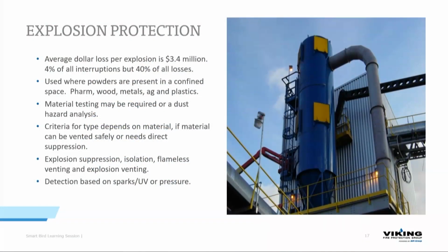So if you've got a product that can be vented out into the environment, it's safe for the environment, you may just want to do direct out to the environment. You can see the explosion panels on the side here. Explosion suppression, isolation, flameless venting, and explosion venting are all different types of explosion protection. Detection is based on sparks that come through the system and get picked up by UV detectors or pressure. And when we're talking about how fast some of these explosion protection systems work, it's milliseconds. So it really has to be really responsive and really fast.